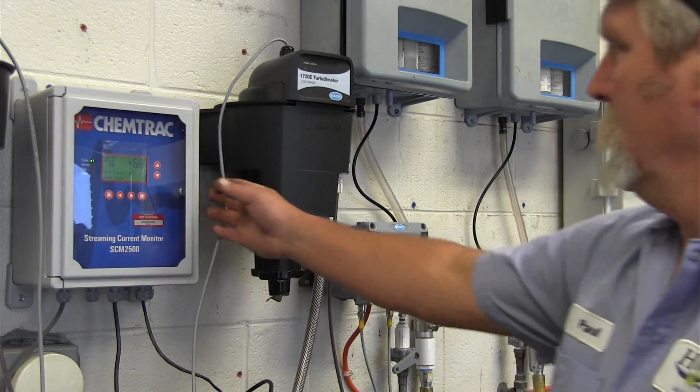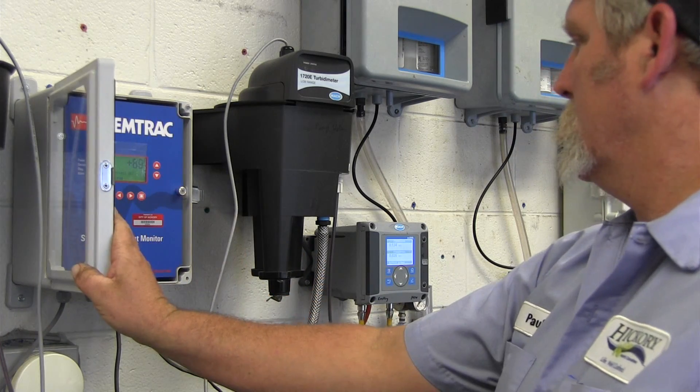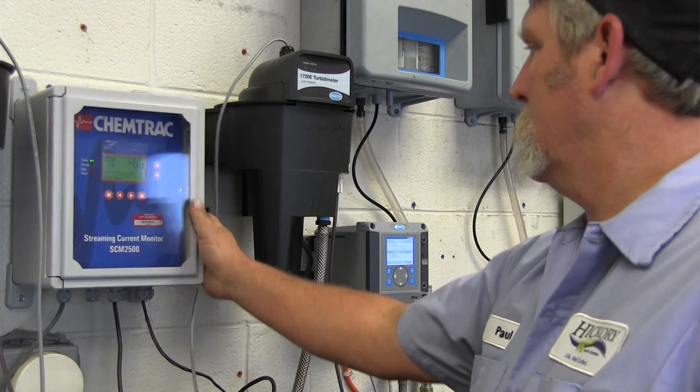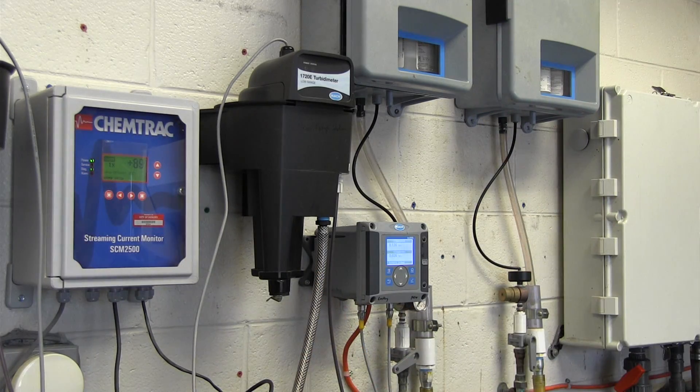It tells us if we're overfeeding our alum or underfeeding, if the conditions have changed or anything that we need to be aware of before we actually have to engage in a jar test. The Chemtrac unit seemed to function much better in the changing conditions. We had a quicker turnaround time on the meter itself and we would get better, more accurate readings.